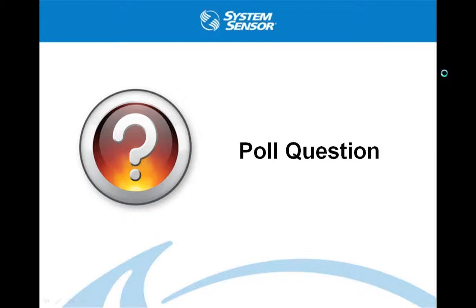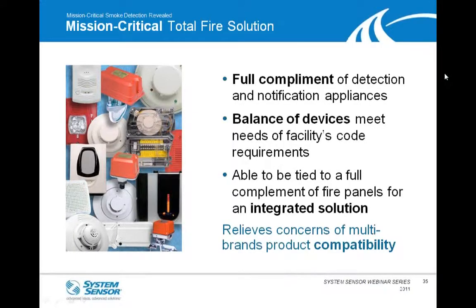Okay, great. So we spent quite a bit of time talking about both the mission critical as well as some of the codes and standards, and really how FAAST can help you meet those codes. I do want to note that System Sensor doesn't just have aspiration, but it has a full complement of detection and notification appliances. The balance of devices outside the aspiration do help meet the other needs of the facility's code requirements. And it's not inconceivable that you would have aspiration in certain parts of even these mission-critical facilities, and then maybe even standard detection or other types of high-sensitivity spot detectors in other areas.